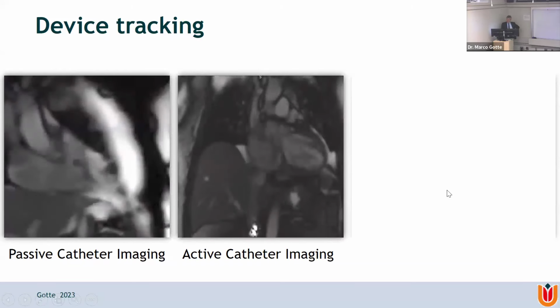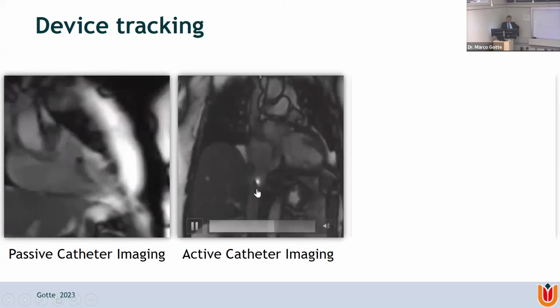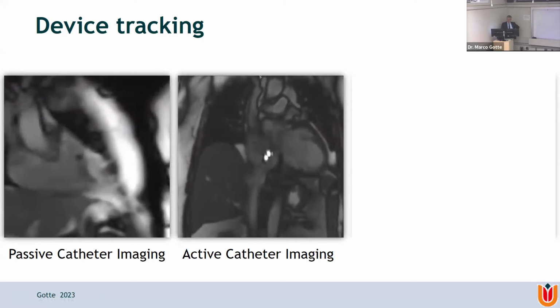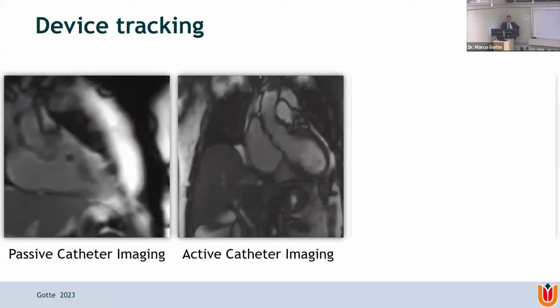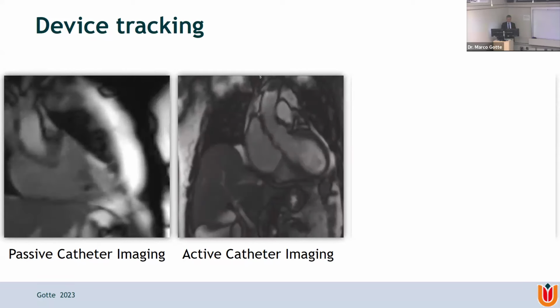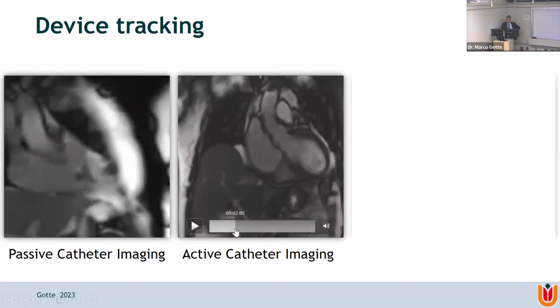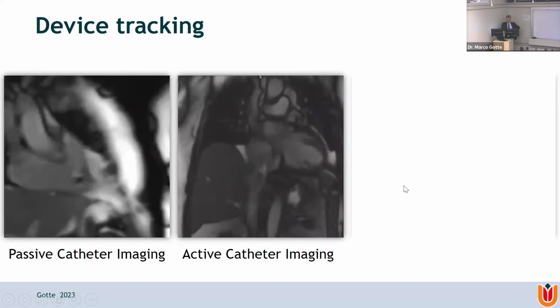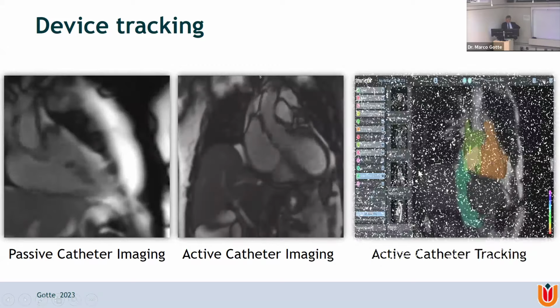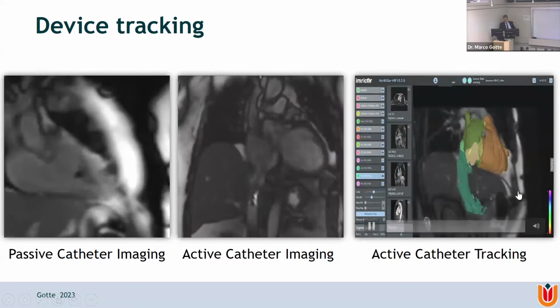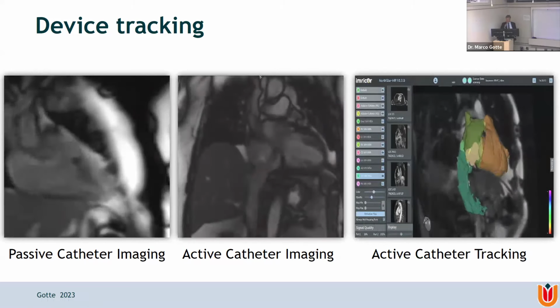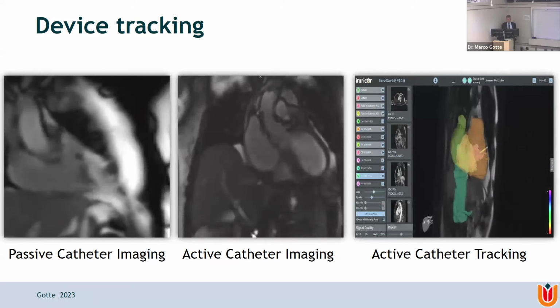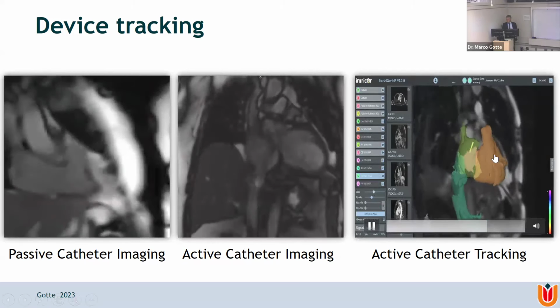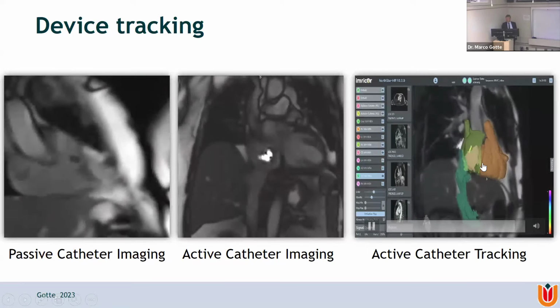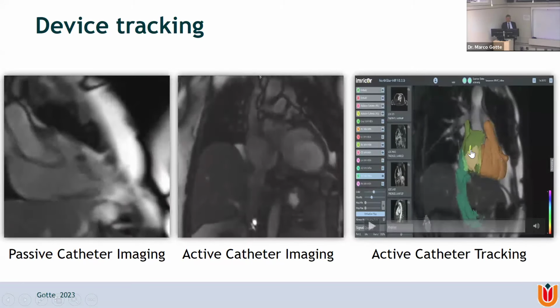The second step is more complicated and requires more equipment. There's a direct coupling between the catheter tip coils and the scanner. So there are two built-in coils in the tip of the catheter, and they are directly connected to the scanner, and the scanner recognizes these tips. This gives you the bright signal coming from the tip, with which you can navigate your catheter. We are now at a stage where we have a kind of mapping navigation system, a Carto maybe version 0.1 or 0.2, but it allows us to visualize the catheters in a 3D shell acquired at that moment, again based on the coils built into the catheter.